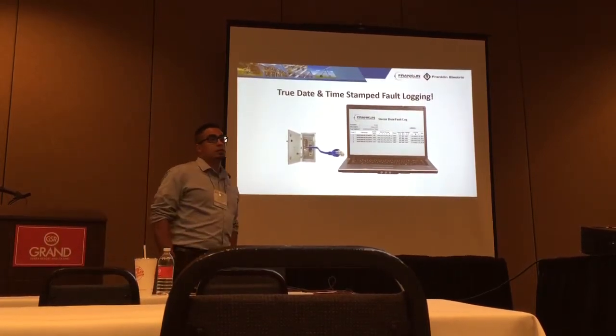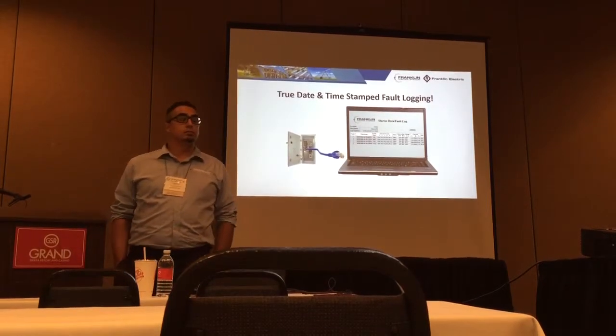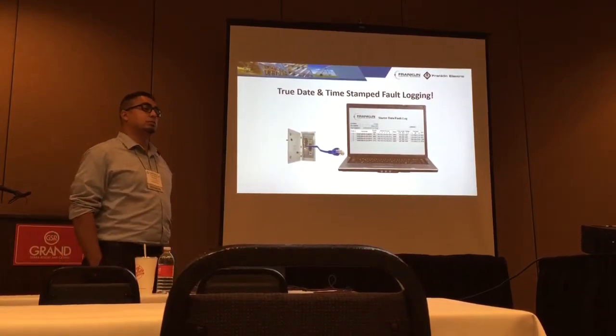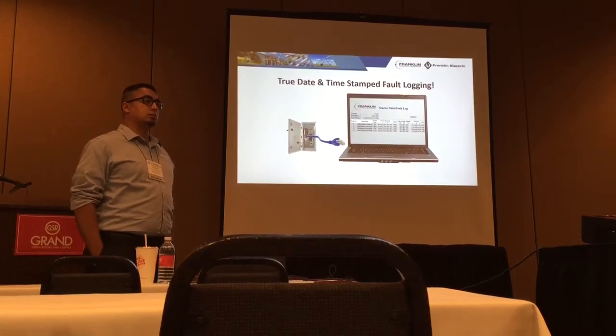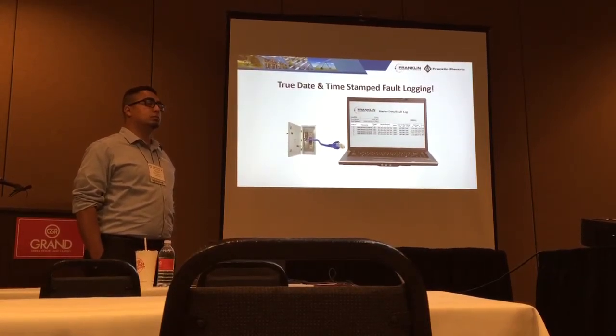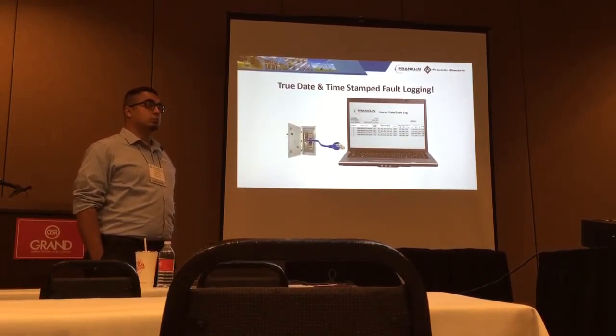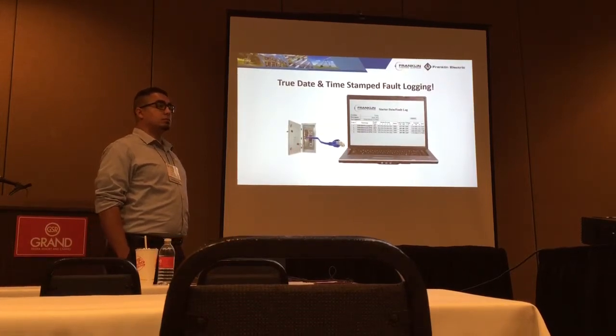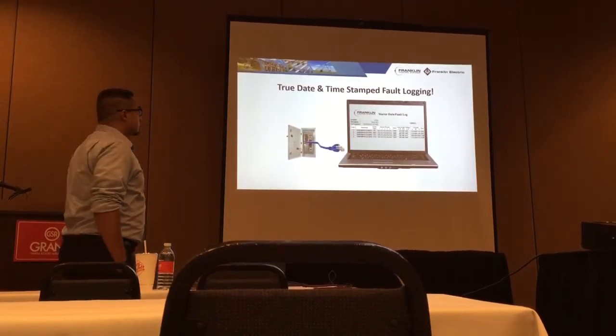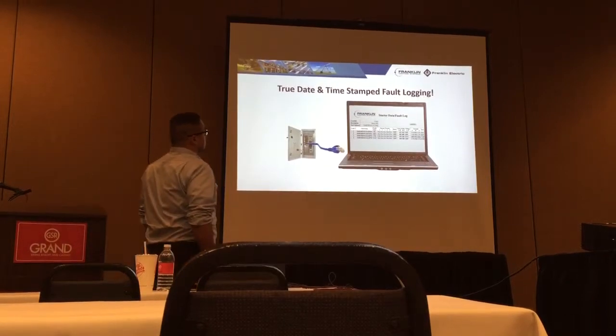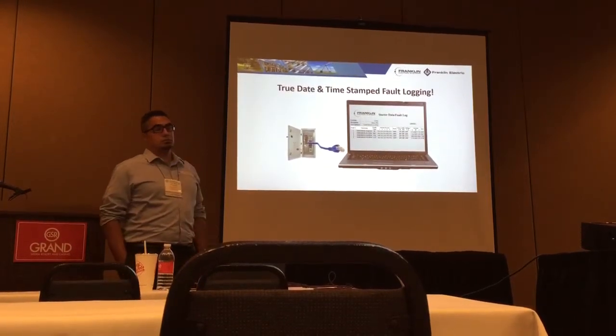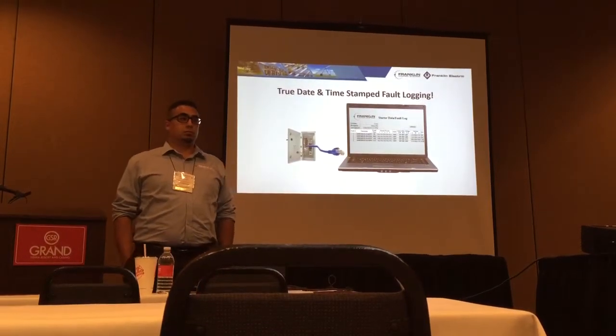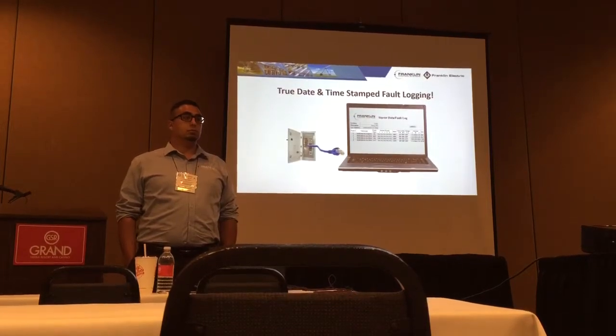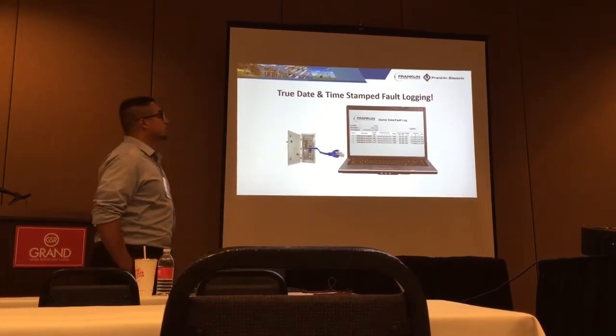For years, it used to be across the line, your standard overloads, and I'm not saying that they didn't need some upgrading to be a little bit more fine-tuned. But is there that big of a substantial difference with all this electronically engineered stuff to protect the motor, to trip out on all these little faults, when the old standby stuff worked for many, many years too without these service call issues?